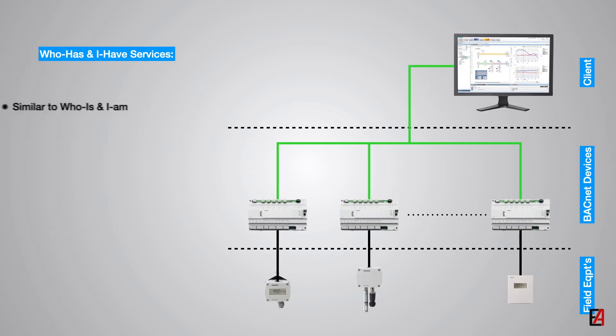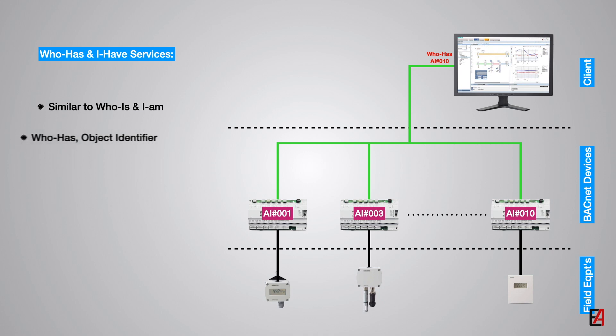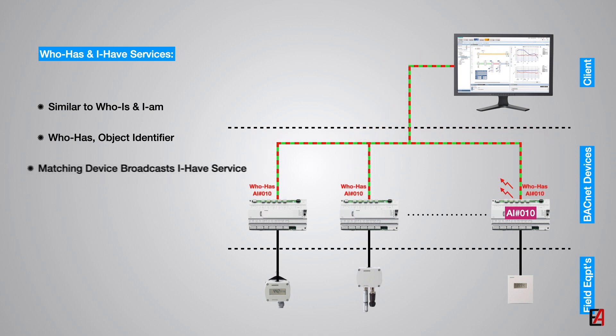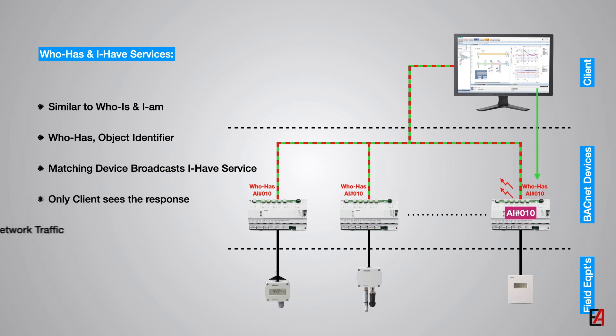The Who-Has and I-Have services are similar to the Who-Is and I-Am service but the Who-Has service adds either an object identifier or an object name. Receiving device which contains an object matching the request broadcasts the I-Have service which will be seen only by the requesting device.